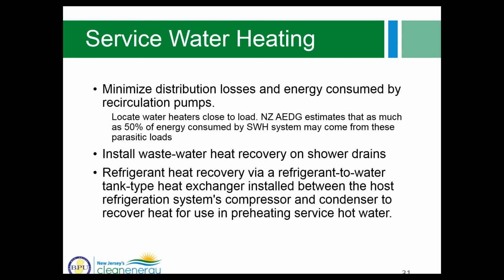Other opportunities related to service water heating include minimizing distribution losses and energy consumed by recirculation pumps. These are not opportunities for credit when you do energy modeling, because with Appendix G we are not accounting for distribution losses, and we assume the same recirculation pump energy in the baseline and proposed design. But as was mentioned by John and reiterated by Keith, we do have final incentive number 3, that is based on actual realized performance, and distribution losses and other parasitic loads associated with service water heating can double service water heating energy consumption. So make sure that you pay attention to these aspects in the building design.